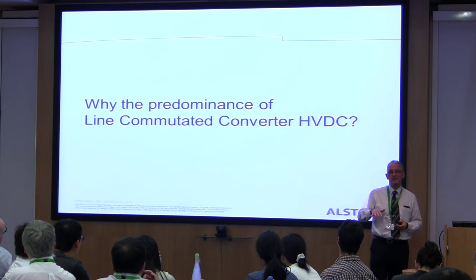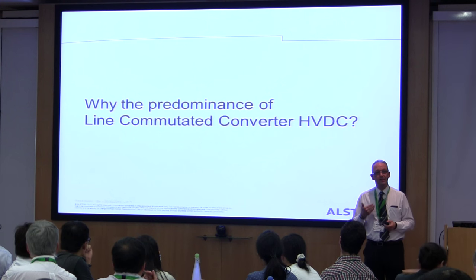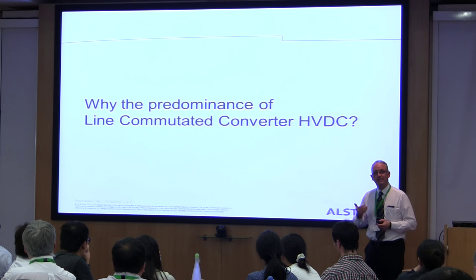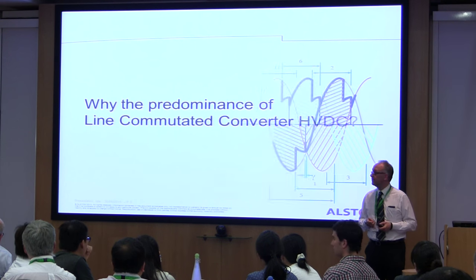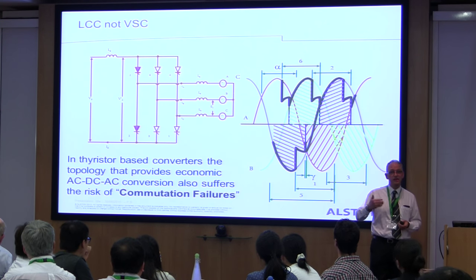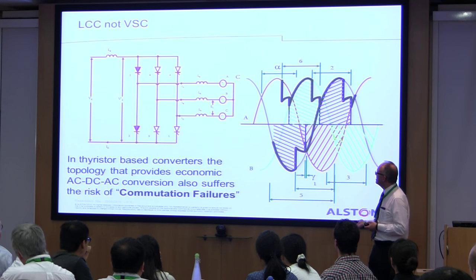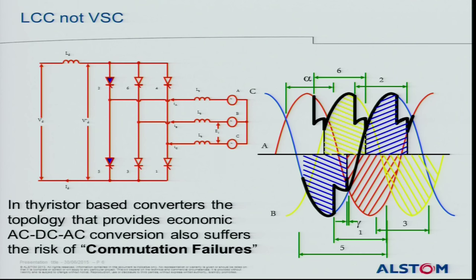To understand voltage source converters and their rapid growth, we need to understand the history and why to date it has been line commutated converters. The early available technology was mercury arc and then thyristors. Thyristors, formed as a six-pulse bridge, carry a risk of commutation failure — a short through the bridge causing a collapse in DC voltage because two thyristors fire at the same time.